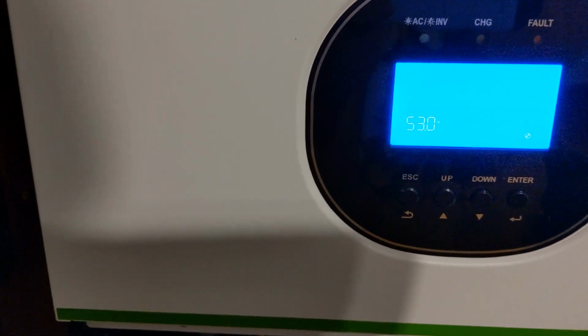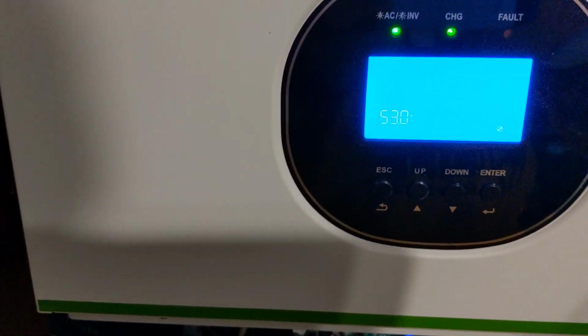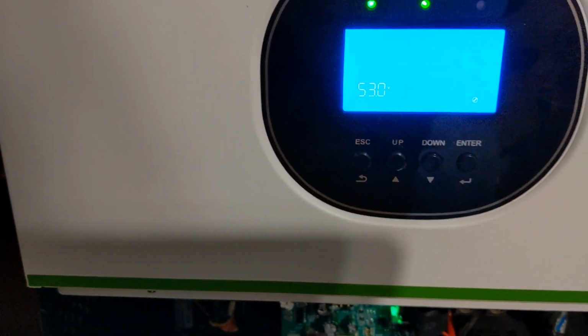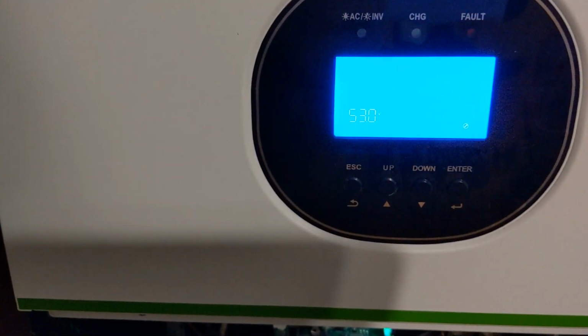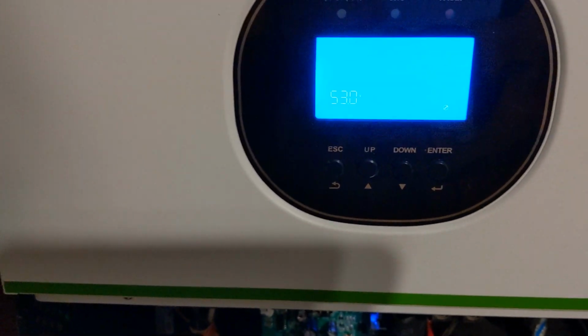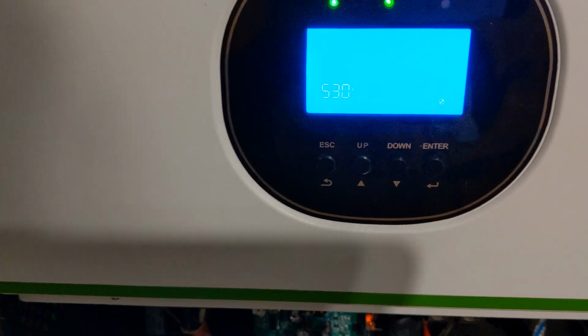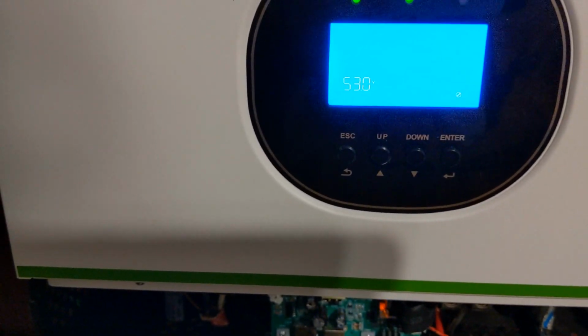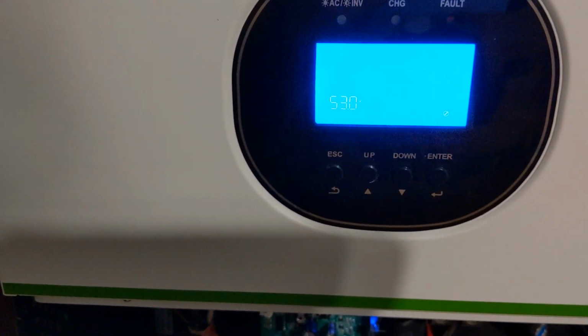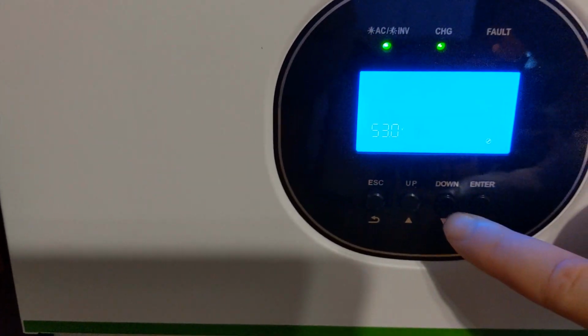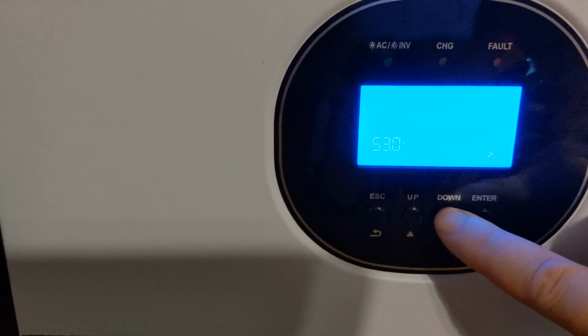And for this one here, you can basically set your settings from 48 volts to 58 volts, so you've got a pretty wide range depending on your battery bank. My batteries are lithium iron phosphate, so I keep mine at about 54.5, 54.6 volts as the peak for topping off the charge. So this still gives me a pretty good range.